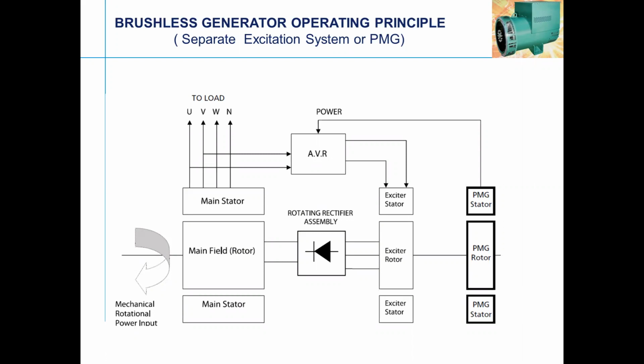You all know fundamentally that when there is a North Pole and South Pole and you keep a rod, because of the magnetic force there is a rotation in the conductor. That is the basic of it, and that is how the PMG works. It has an independent voltage which can feed the AVR. There is some advantage on motor starting and for nonlinear loads in this application. So preferably some designers use a PMG for larger generators, to have a black start or higher motor starting.